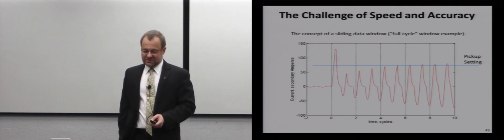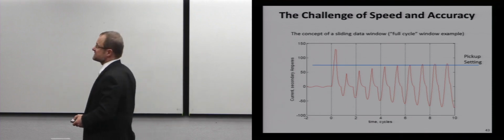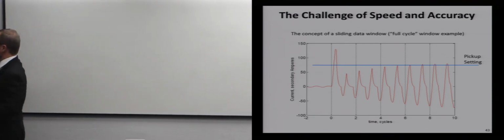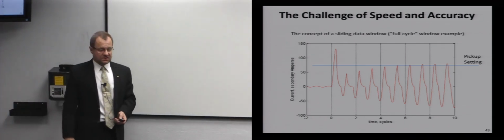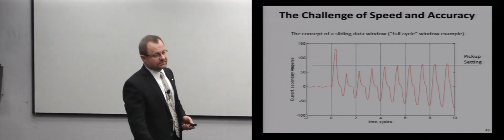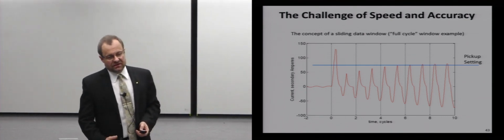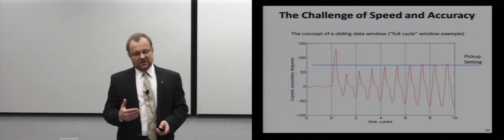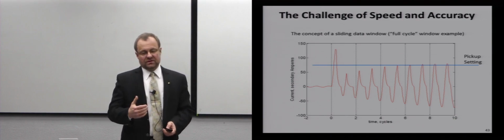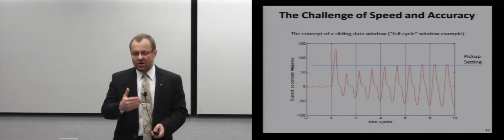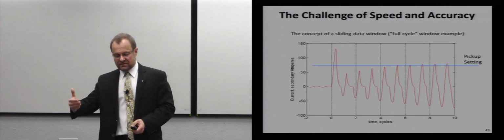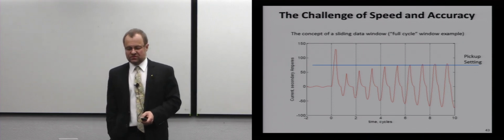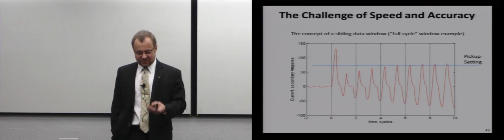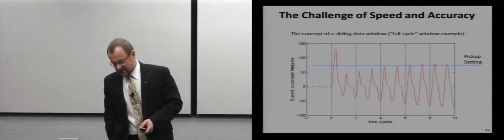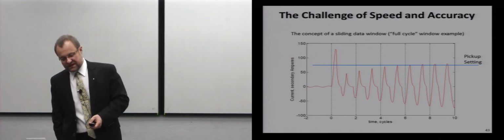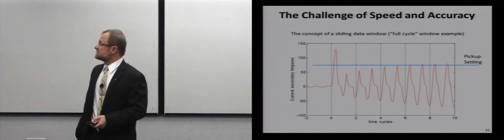And time is passing, and eventually you realize that yes, you should trip, but that information is truly available only here. So this is what we try to do, right? We try to decide whether the operating conditions are such that we should trip, assert the output. We want to do it fast, but we don't want to be wrong. We want to trip only when the conditions are that we should trip. Otherwise, people call it, rightfully so, a misoperation, and they complain about the relay. That's not that bad. If we trip and there is a blackout, then it's really serious. So that's what we try to do.